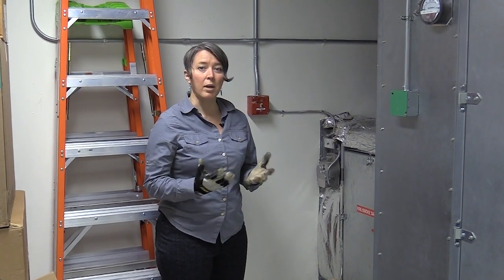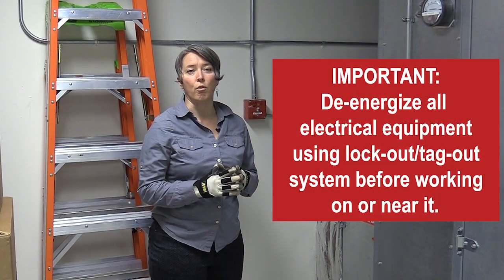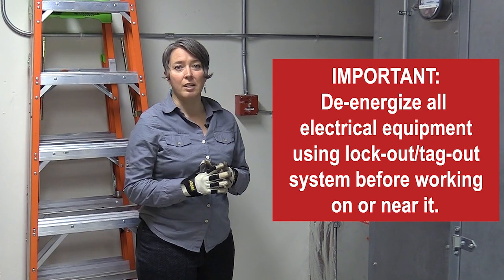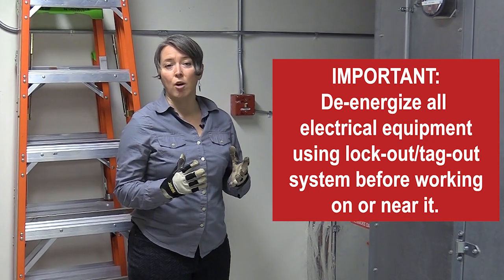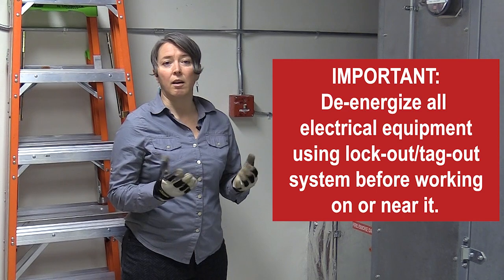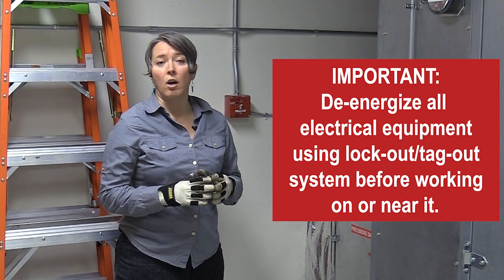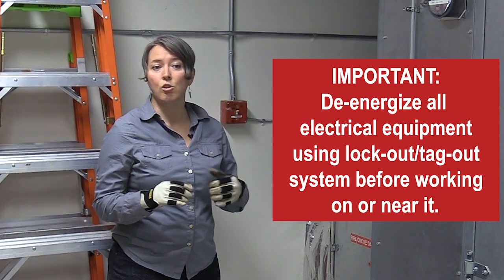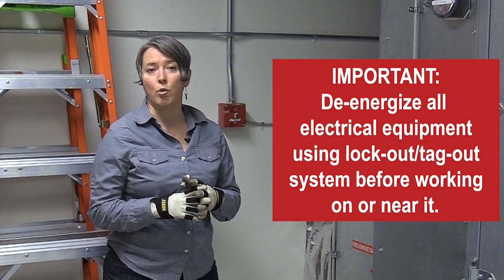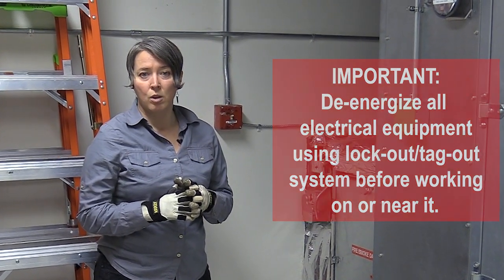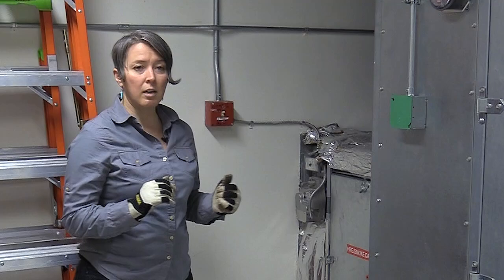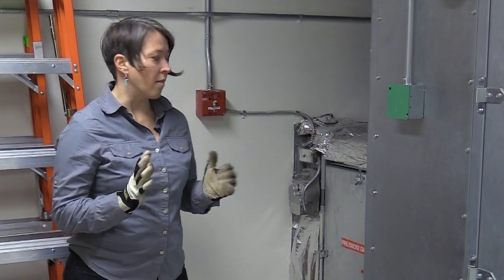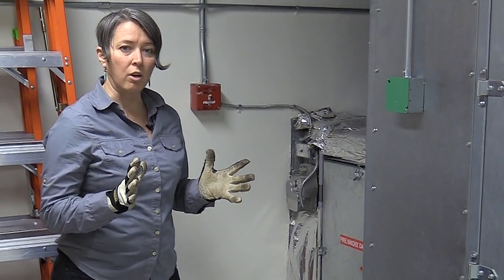Okay, so I'm going to go ahead and place our data loggers, and I want to make a note about safety. It's really important to de-energize any fans using a lockout tagout system, any electrical equipment at all, before you place sensors or work near any kind of equipment that could be hazardous. So I've got the fan de-energized here. Everything's shut down, and it should be safe to open the access panel. So we have our panel open here.